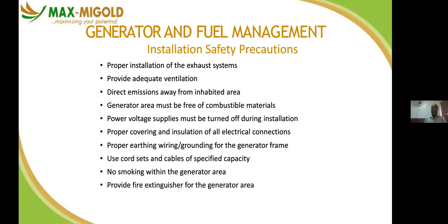Direct emission away from an inhabited area. Don't allow your smoke to circulate where other people are living. The generator area must be free from combustible material. Why? Because if there is an outbreak of fire, instead of using a single fire extinguisher to quench the generator, because of the other combustible material, you'll be looking for additional fire extinguishers, because those combustibles will support the fire and you may not be able to quench it. So that's why you are advised to set your generator free from combustible material.